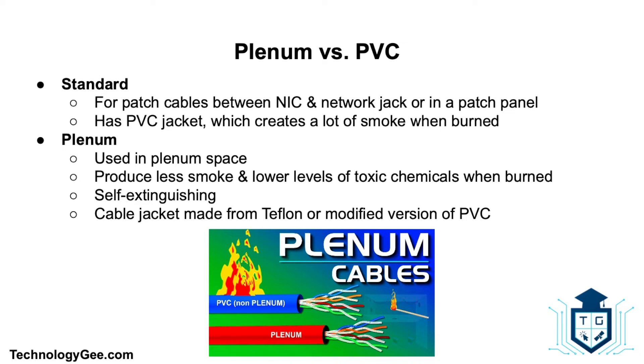Next, plenum versus PVC. There are two categories of twisted pair cabling in terms of fire rating. Standard cabling is suitable for patch cables between network interface cards and the network jack; PVC jackets can create a lot of smoke when burned. Plenum cabling is designed for use in plenum spaces — areas that facilitate air circulation such as ventilator shafts, under floors, or between suspended and permanent ceilings. Plenum cables produce less smoke and lower levels of toxic chemicals when burned, are commonly self-extinguishing, and may be made from Teflon or a modified PVC.